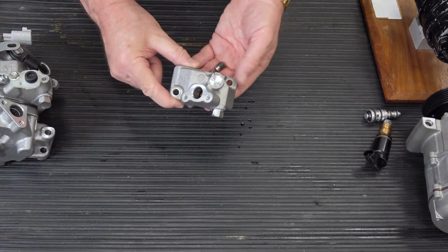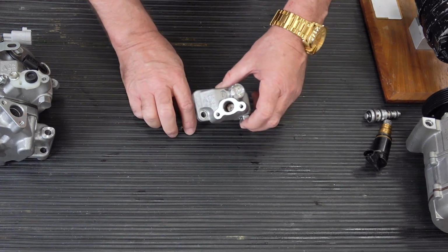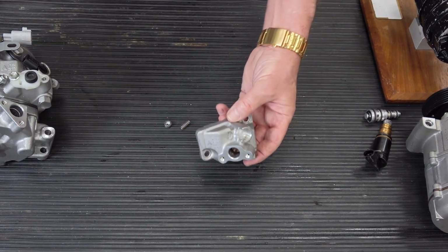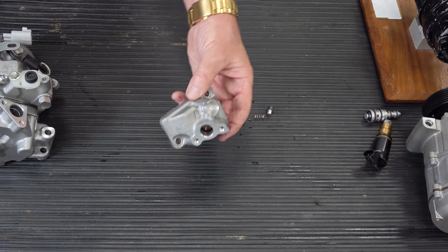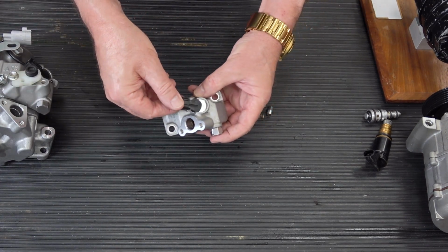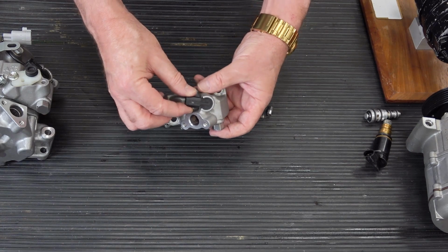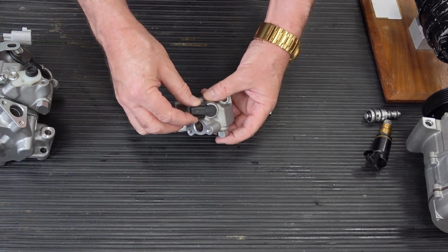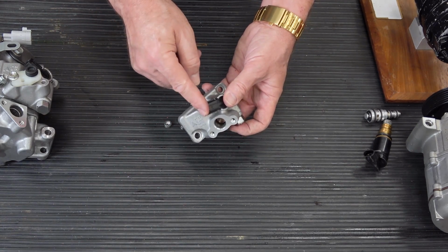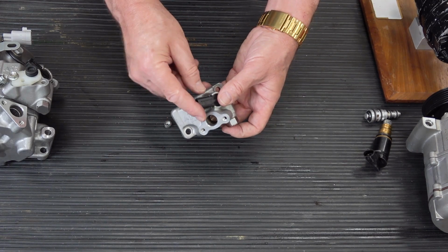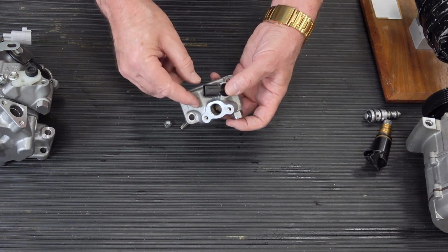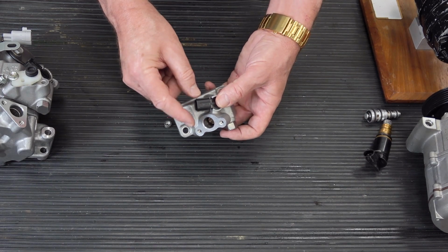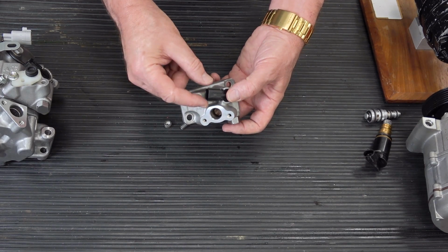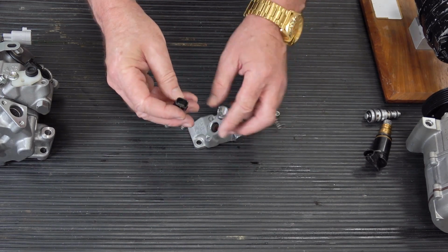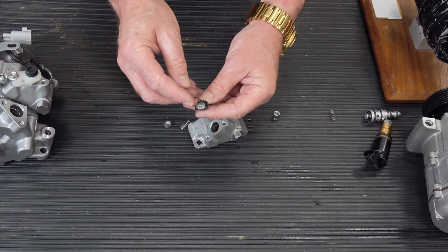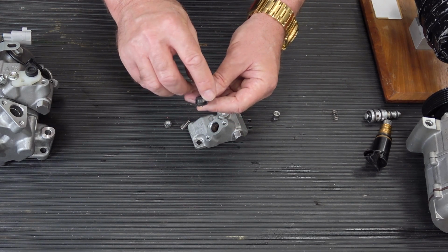So if we look here, here's the discharge port from the compressor that we were just looking at. Do you see there's an area here? This little piece here is the refrigerant volume flow sensor. This sensor does not make contact with the refrigerant. It's just clipped to a snap ring that holds it to the outside of the discharge manifold. The way this works is, just like a MAP sensor or TPS, it's got a 5-volt reference, a ground, and a signal.